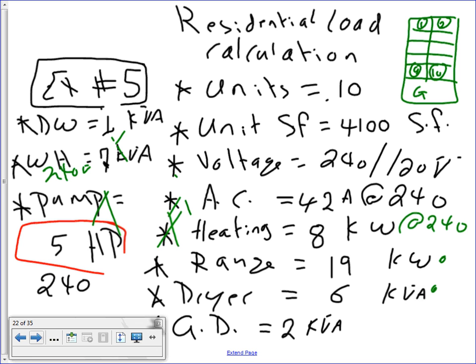10 units. Each unit is 4100 square feet, they're richies, so they're living in apartments of 4100. That's almost as big as my house, if not bigger. Don't ask me why, they have cash. So 4100 square foot, that's a big apartment. A lot of apartments are barely 1,000, 1,200, maybe 2,000. Okay, the voltage is 240/120. Each one of them has an AC unit of 42 amps at 240, heating 8 kW at 240, range 19 kW, that's a big range, dryers 6 kW, garbage disposal 2 kW, dishwasher 1 kW, water heater at 240, 7 kW, pump 5 horsepower at 240.